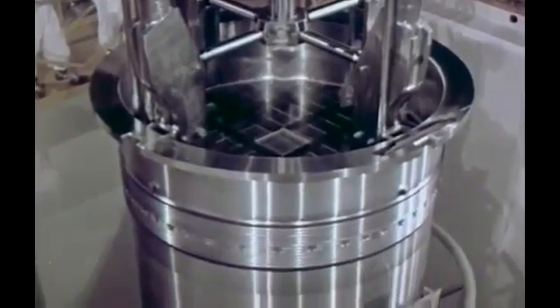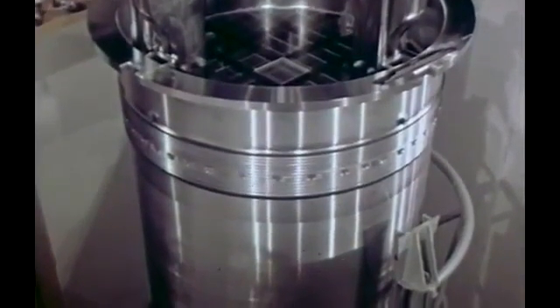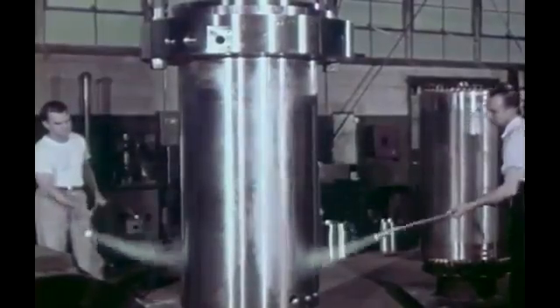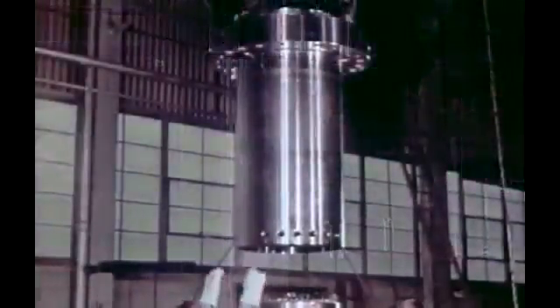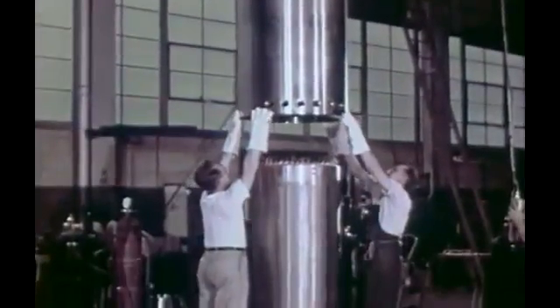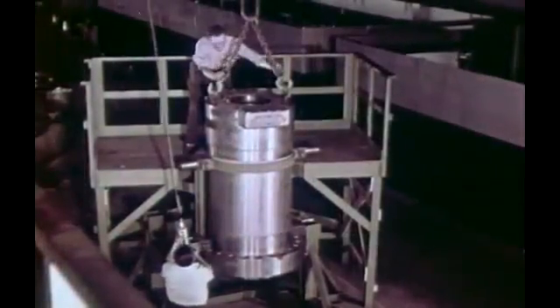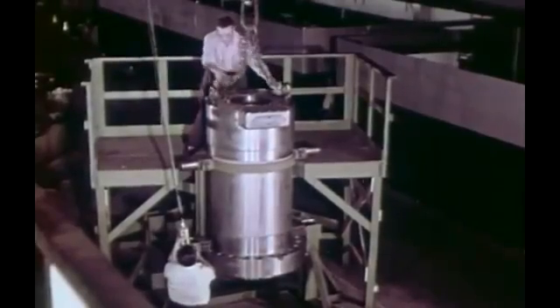The shipping port plant has a large number of newly developed items of equipment to ensure safety and reliability. Typical of these are zero-leakage canned motor pumps. In this design, no shaft seal is necessary. Metal cans enclose both stator and rotor. Primary water circulates between them, lubricating the bearings and cooling the induction motor. A separate water supply cools the stator coils.